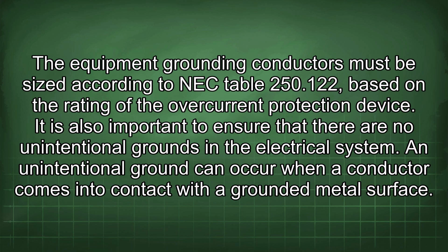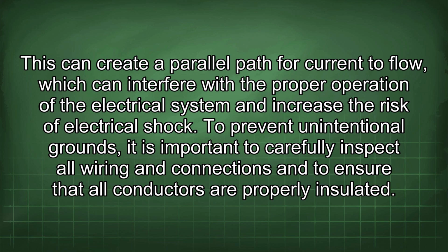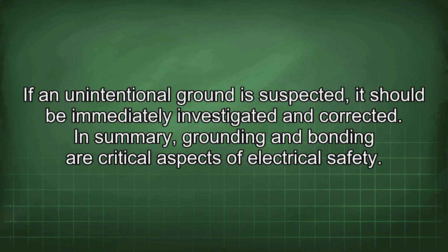It is also important to ensure that there are no unintentional grounds in the electrical system. An unintentional ground can occur when a conductor comes into contact with a grounded metal surface. This can create a parallel path for current to flow, which can interfere with the proper operation of the electrical system and increase the risk of electrical shock. To prevent unintentional grounds, it is important to carefully inspect all wiring and connections and to ensure that all conductors are properly insulated. If an unintentional ground is suspected, it should be immediately investigated and corrected.